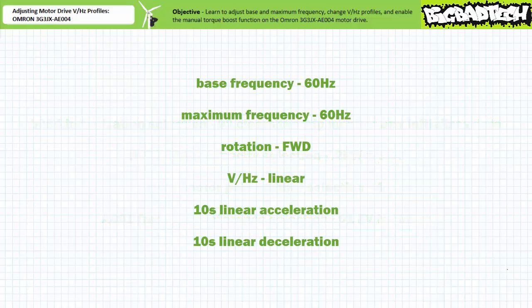This start state establishes a 60 hertz base frequency, a 60 hertz maximum frequency, forward default rotation, a linear volts per hertz ratio, a 10 second linear acceleration time, and a 10 second linear deceleration time among other properties. This motor drive is now ready for today's activities.